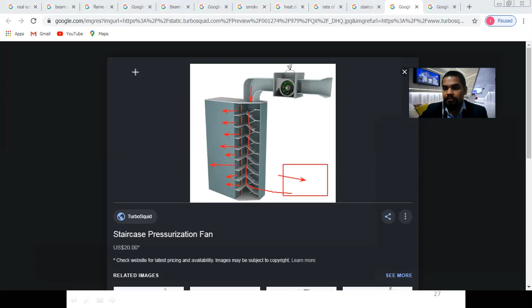So in that case, we pressurize the staircase by giving it air from the fan. What will happen? The more pressure will be there, so smoke will not come to the staircase, because the pressure will be in that direction, so the air will go in that direction. Your staircase will be free from smoke, and the smoke on the floor will not be able to come to the staircase, and the people using the staircase will use it very easily, and the oxygen level of the staircase will be more, right?